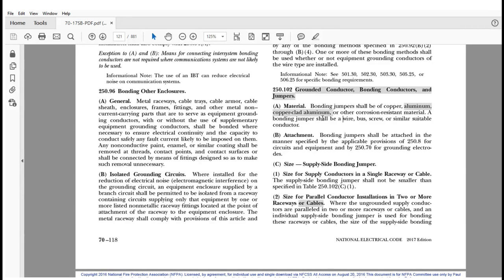So the other thing is to explicitly add aluminum and copper clad aluminum as the materials for acceptable bonding jumpers. It really harmonizes with the language that is found in 250.62 that recognizes aluminum and copper clad aluminum as a corrosion resistive material. Okay, many times people were left wondering whether or not it was, and I can tell you, as a manufacturer, or working for a manufacturer of aluminum and copper, that aluminum is very corrosion resistant in its application. Okay, so this change will help avoid any confusion.